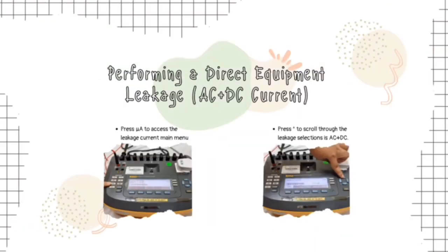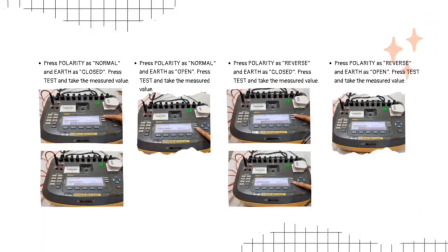Next is performing a direct equipment leakage AC plus DC current. Firstly, press microampere to access the leakage current main menu as it shows in the figure. Then press the direction symbol as shown in the figure to scroll through the leakage selection to AC plus DC. Then press polarity as normal and earth as closed. Press test and take the measured value. Next, change the polarity as normal and earth as open and press test for the result.